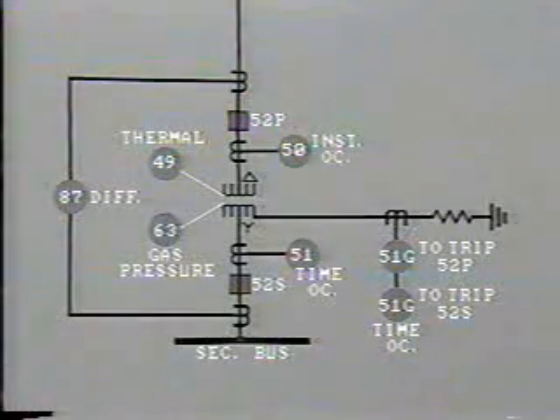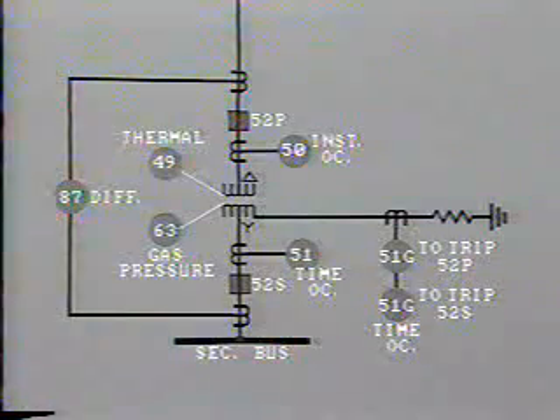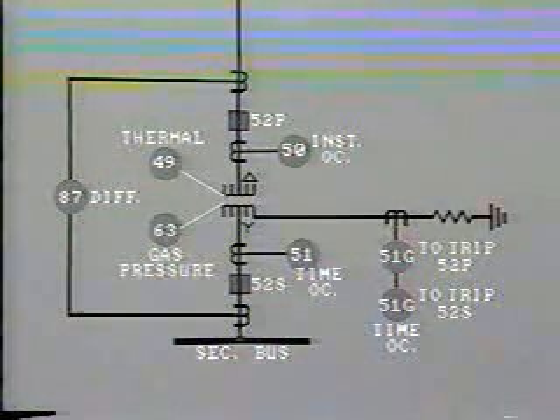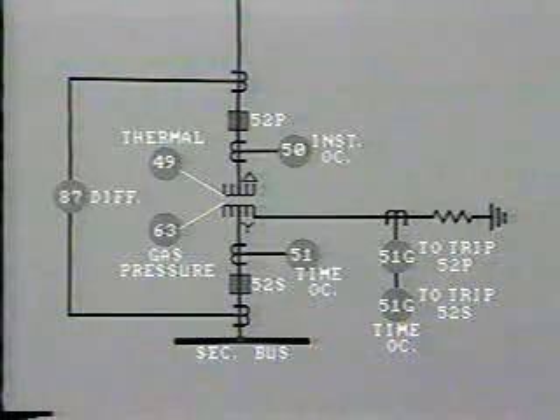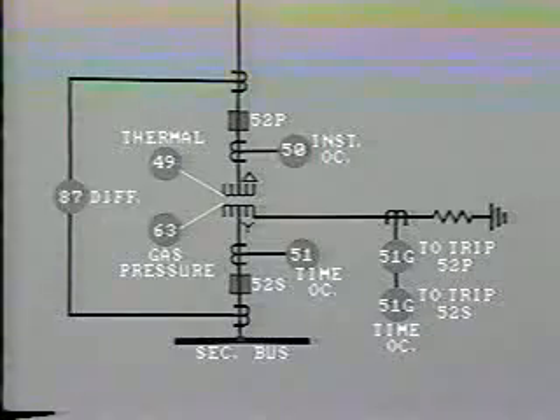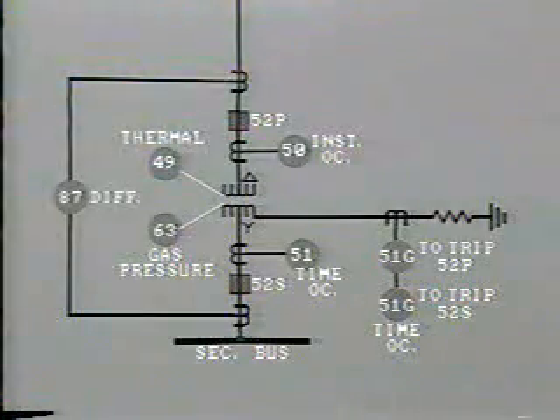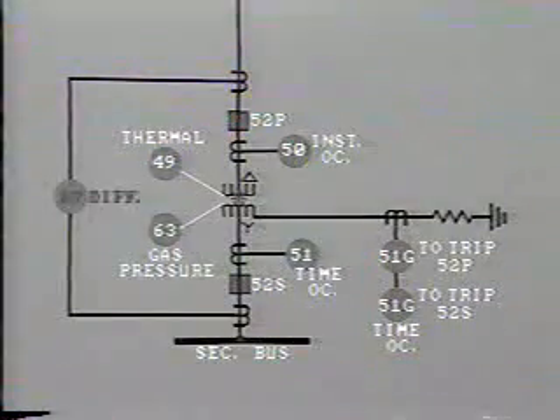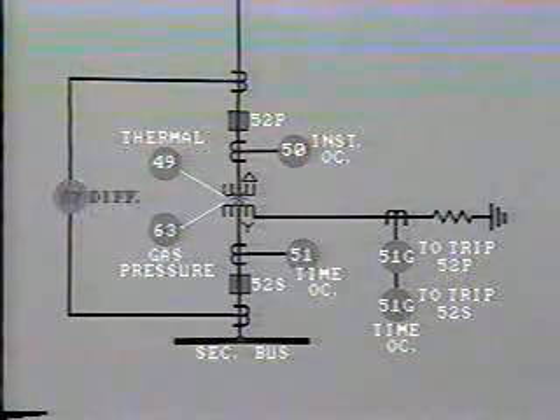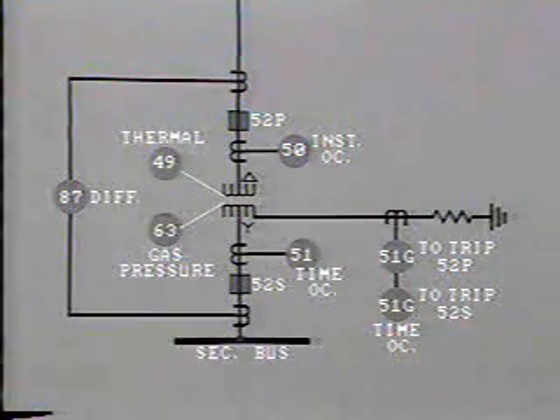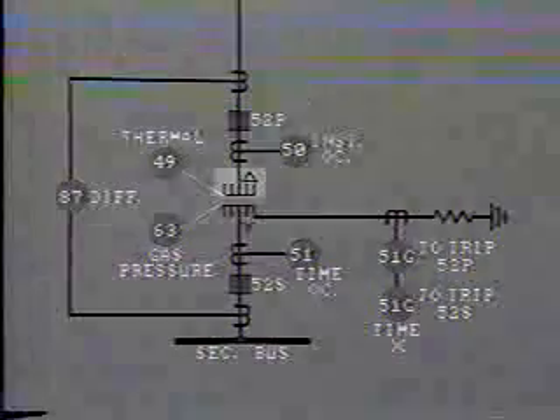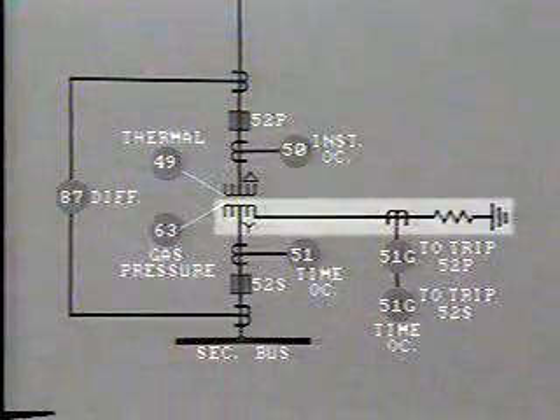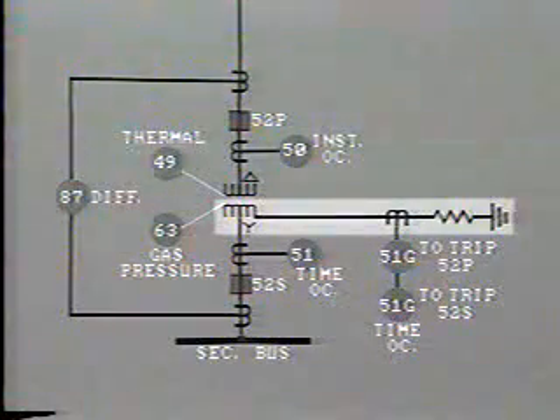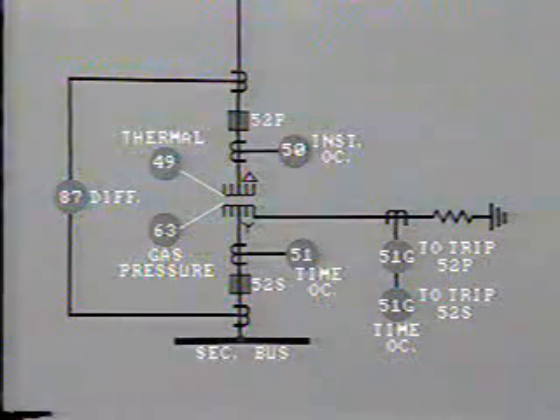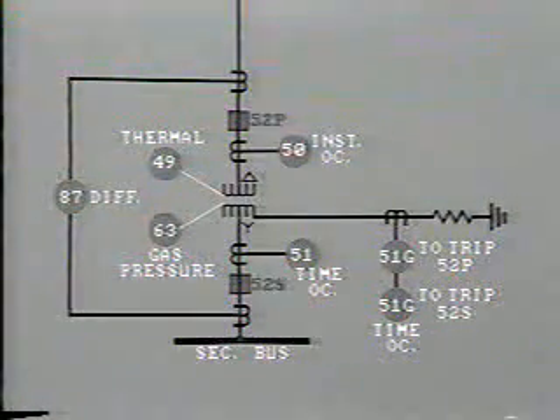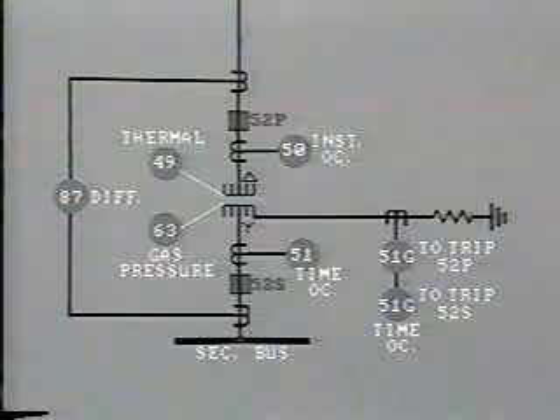But as you probably know from experience, you soon get accustomed to certain numbers, especially those referring to protective devices. Every time you look at a schematic and see the number 87, you know that this refers to a differential protection relay. In this case, differential protection across the primary and secondary of a transformer. What else does the diagram tell us? Well, we can see that the primary is delta connected and the secondary is Y grounded through a resistance. The circuit breakers are represented by 52P primary and 52S secondary.